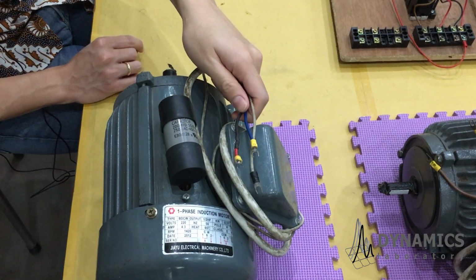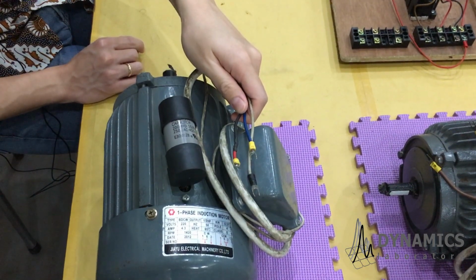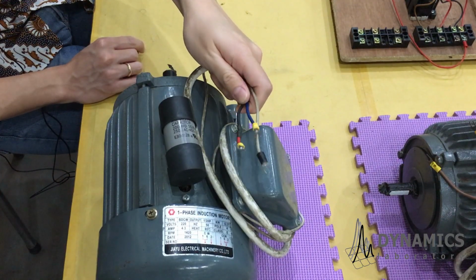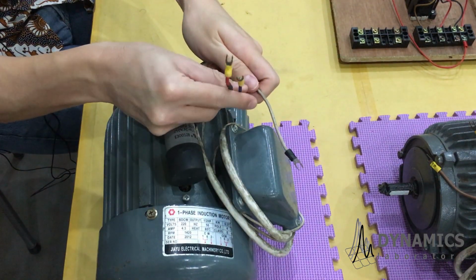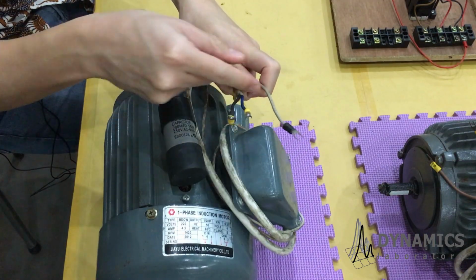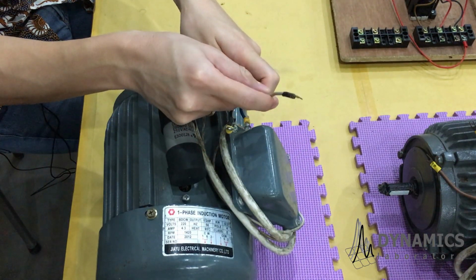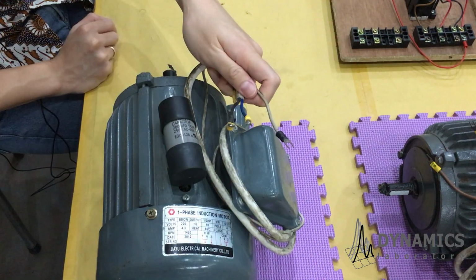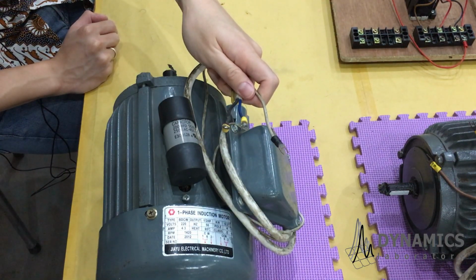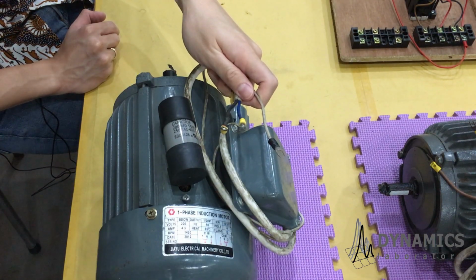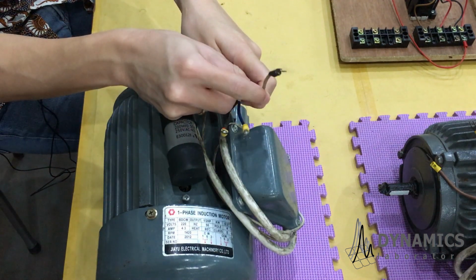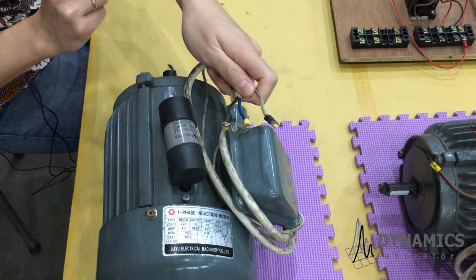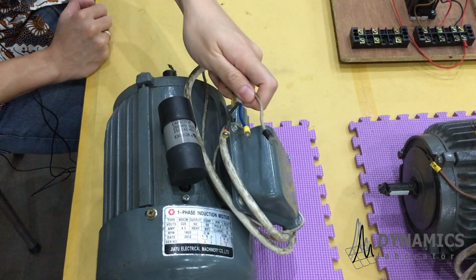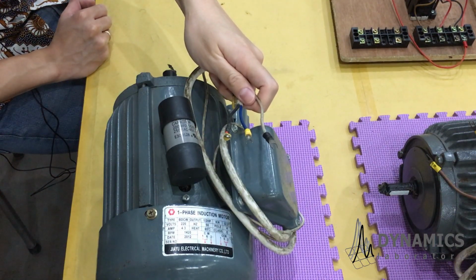How does the one-phase AC motor work? In our one-phase motor, it has 3 cables. 2 cables represent the main winding, meanwhile the last cable represents the auxiliary winding. Actually, each winding should have 2 cables, right? To represent each end of the winding. But why does the auxiliary winding only have one cable? Because one end of the auxiliary winding is already connected to the main winding as shown in the module.